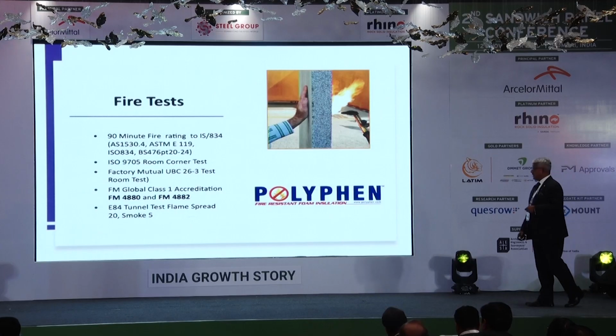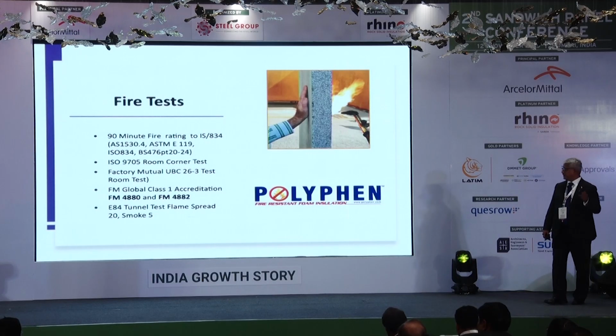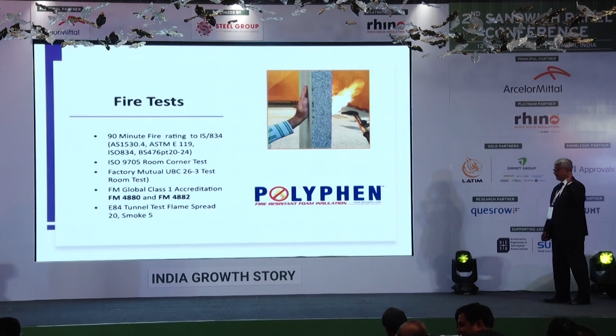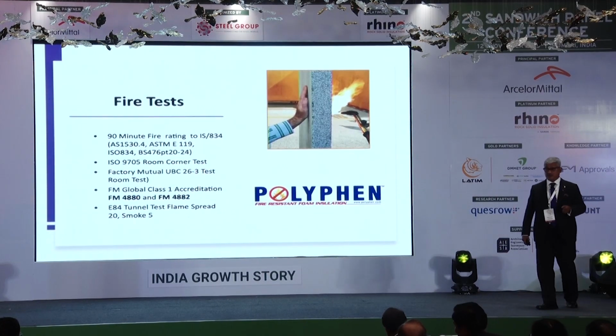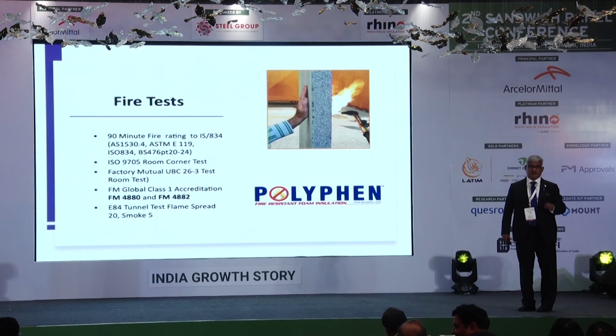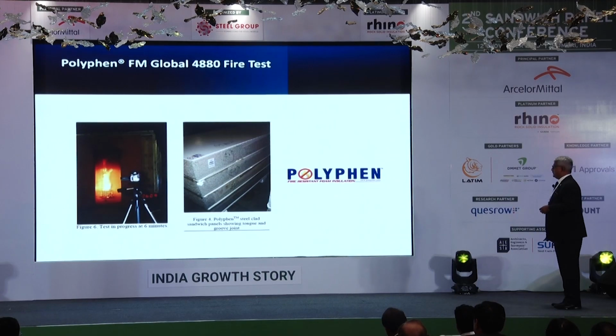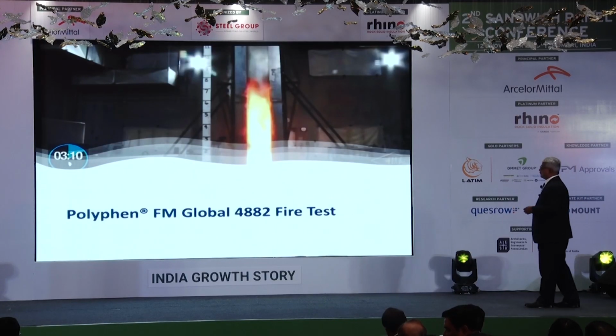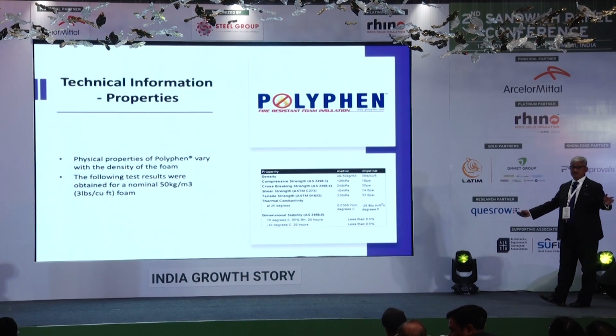Just to summarize: 90 minute fire rating, ASTM E119, the major highlight, ISO 834, BS 476 part 20, 9705 room corner test, UBC 26. I think Yasser gave an excellent presentation and video, 4880, 4882. Somebody mentioned smoke, and these high-tech facilities are very much concerned about smoke, even the life safety. So give proper attention here. So these are certain tests. You saw this test. I will not spend much time. These are the results for the 4880 corner test, 4882. See the scale. These are real-time, practical, real-scale tests.